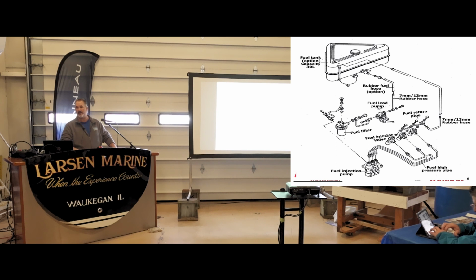We also do something called fuel polishing, which doesn't just clean the fuel, it also cleans the tank. We put an additive in the tank called AFC 705, which breaks down any dirt or algae on the walls of the fuel tank and suspends it within the fuel. Then we cycle that through several times, cleaning not only the fuel but the tank itself. Otherwise, if you've got crap in your tank and you empty the fuel and put new fuel in, you're just putting fuel back into a dirty tank.